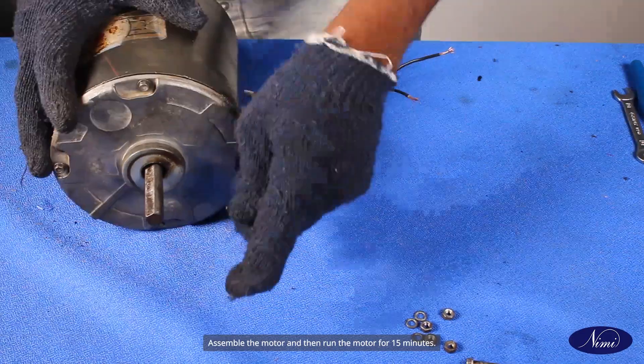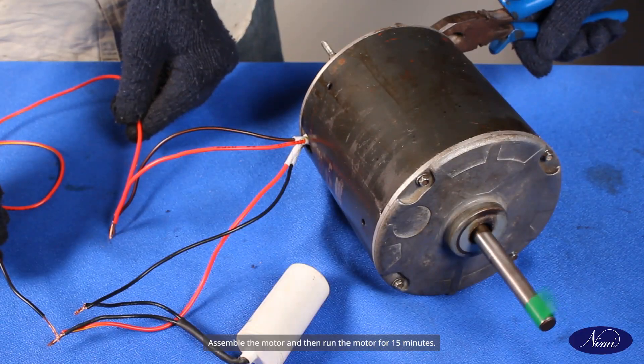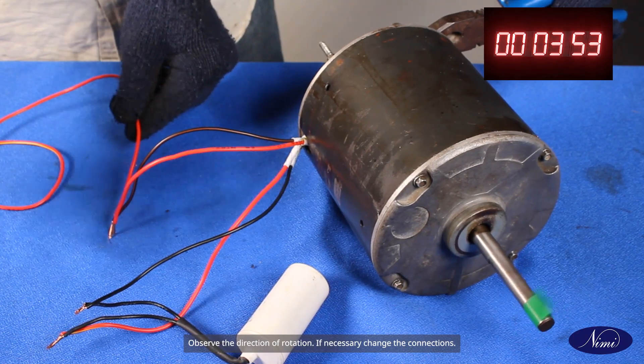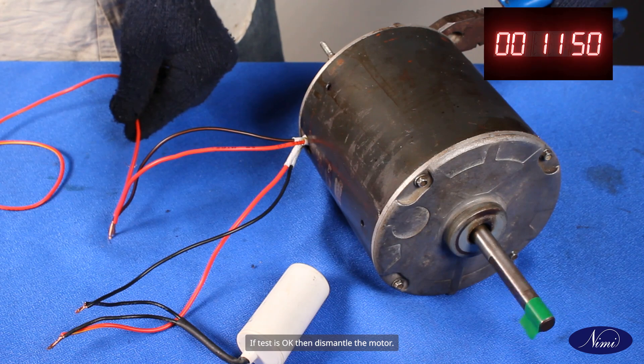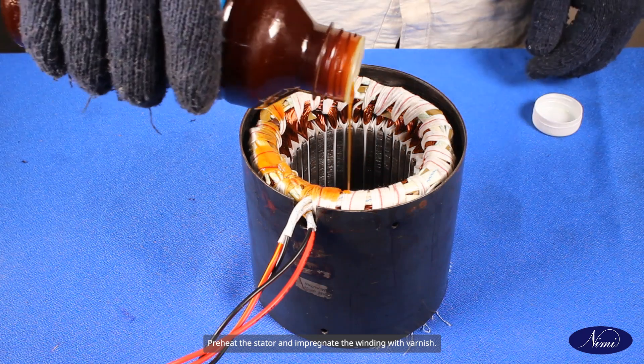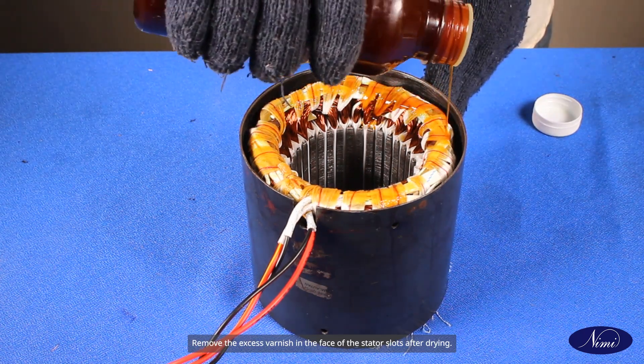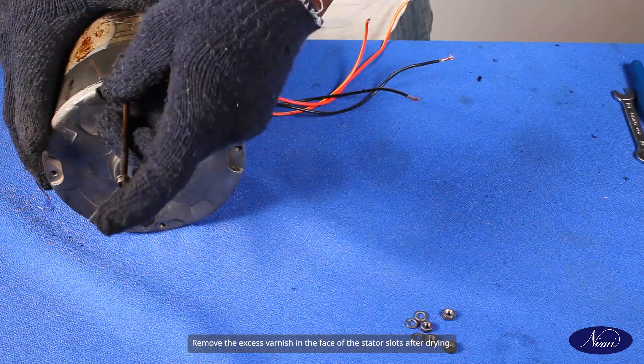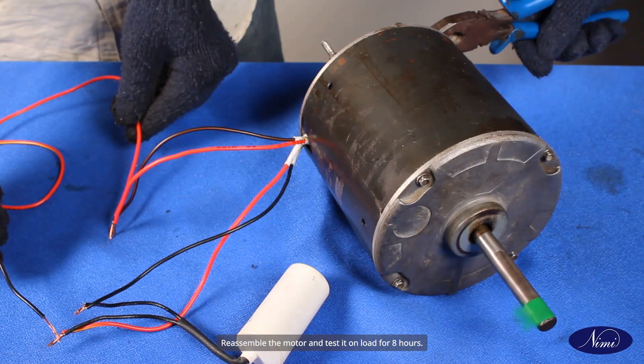Assemble the motor and then run the motor for 15 minutes. Observe the direction of rotation. If necessary, change the connections. If test is okay, then dismantle the motor, preheat the stator, and impregnate the winding with varnish. Remove the excess varnish in the face of the stator slots after drying.